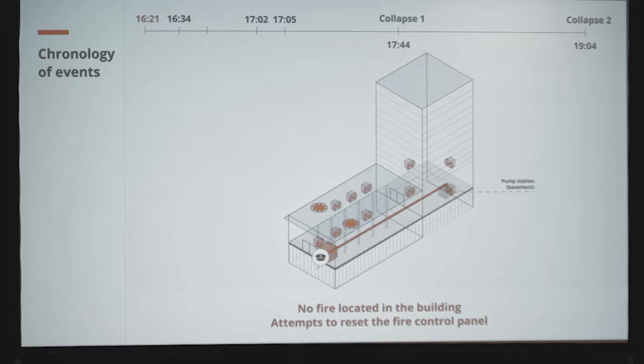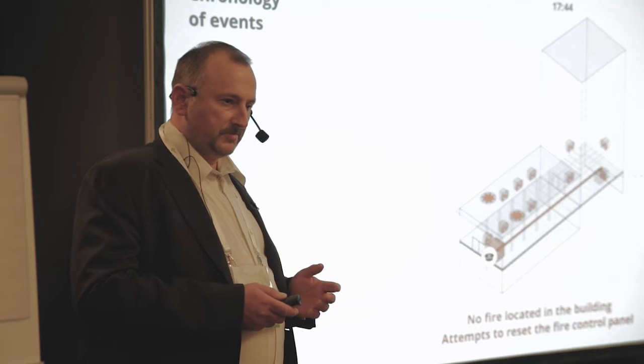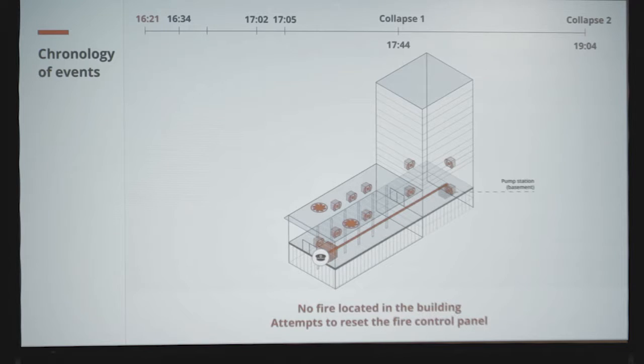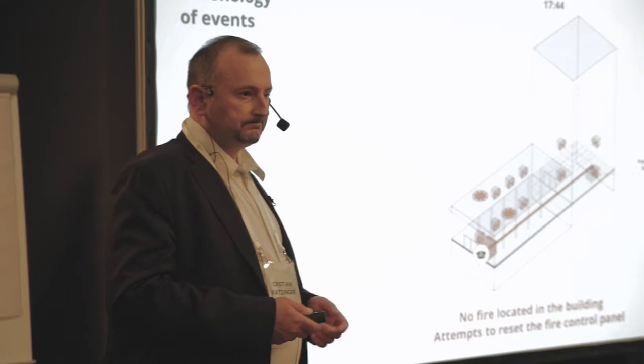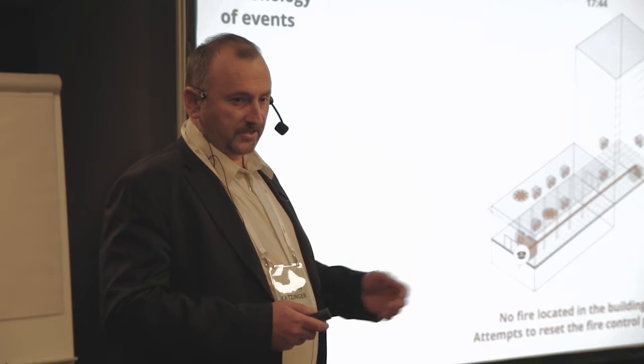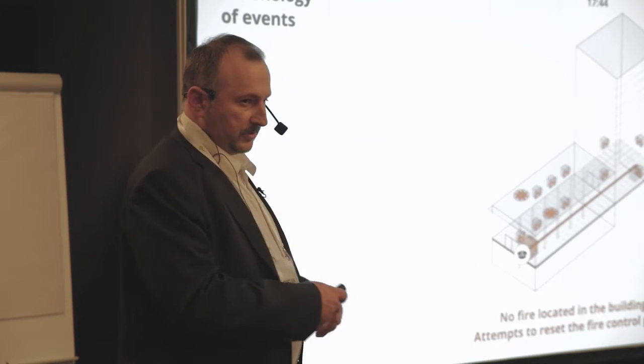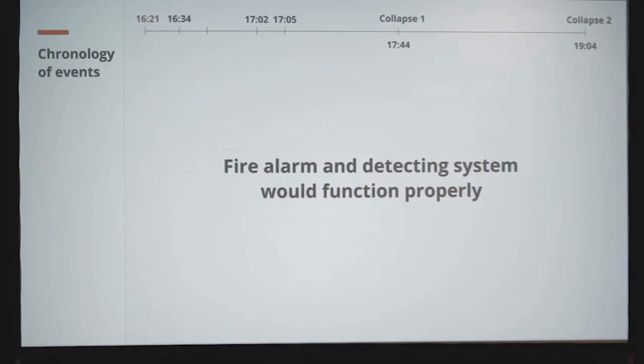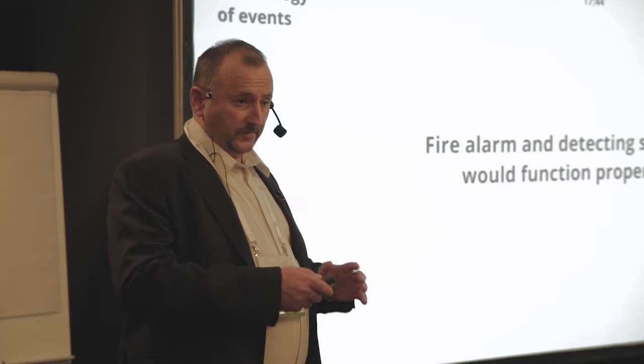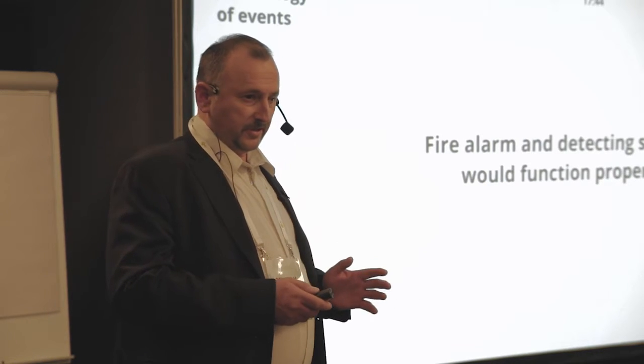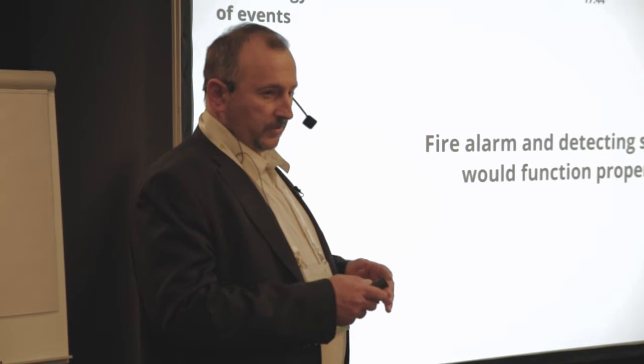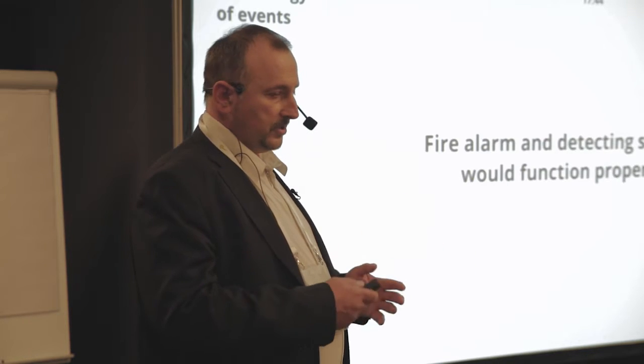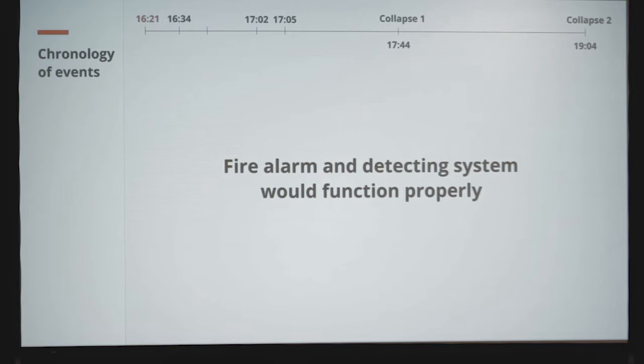The security attempted to reset the fire control panel several times. Normally it would work, but in case of the pump station, it doesn't work because the valve is still open. So the alarm is already existing. Even if you are exiting the fire alarm mode, it will shortly come again. All the other detection systems we had inside the building were still functioning properly. If there would have been a problem, for example a fire inside the first floor, the smoke detection system would have given alarm to the control unit. You would have seen it, everything.